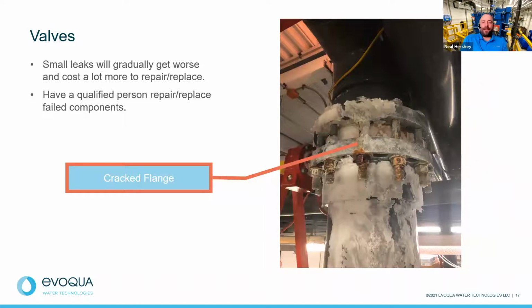Back to that planning part, a small leak will gradually always get worse, and it's going to cost a lot more to repair and replace later on. Have a qualified person do this. It may seem like a basic repair, but usually those repairs end up being a lot more difficult than they appear. In this example, there's just a cracked flange, which should be straightforward to replace. However, as you can see, it wasn't quite the case. It was a bit more involved to cut those bolts out and get everything running again, where if it had been done early on, the bolts probably would have come out easily and it would have just been a matter of replacing that flange. Instead, we had to grind everything out and replace a lot more components.